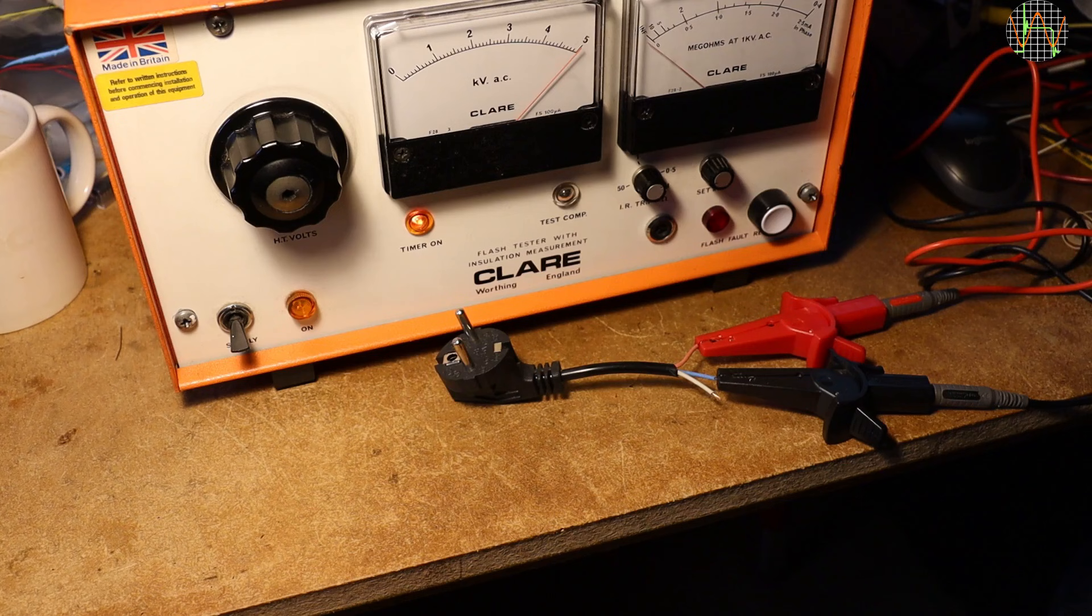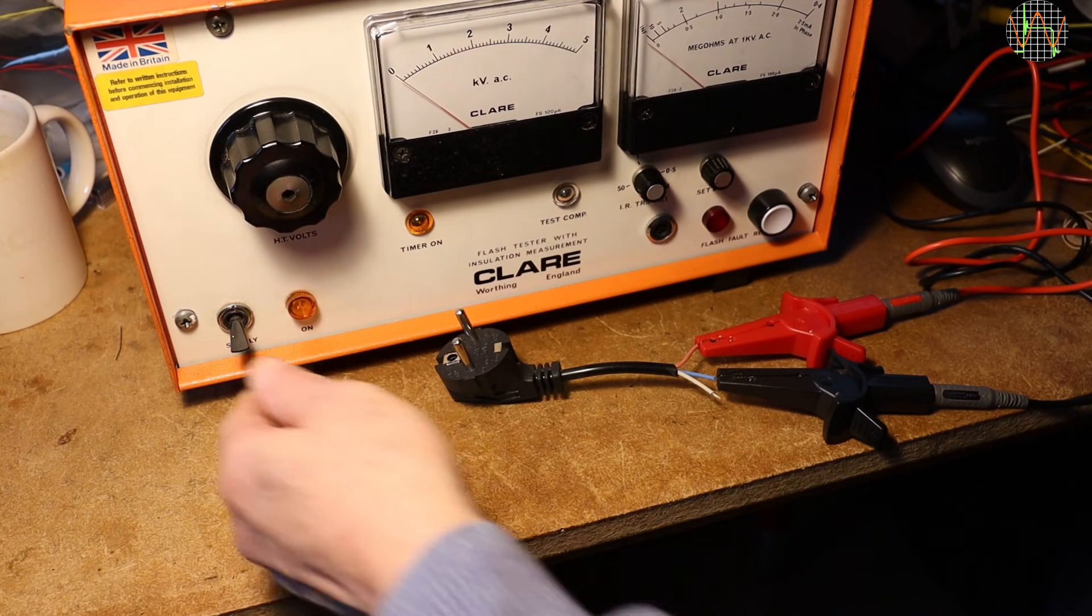This is the 5000V for 10 seconds test. Well, it passed this test just fine.